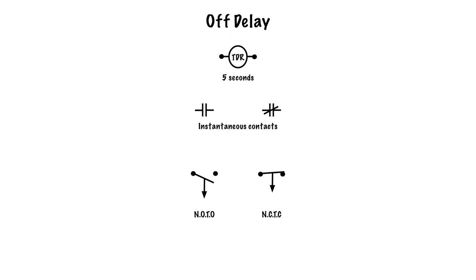The big difference between an off delay and an on delay is that the timing for these contacts begins when the relay is de-energized, after it has been energized. So when TDR energizes, what was once a normally open contact becomes closed, and what was once a normally closed contact becomes open — that happens instantaneously. For the off-delay contacts, they also respond instantly: the normally open time-to-open contact will close instantly, and the normally closed time-to-close contact will open instantly, as long as TDR is energized.